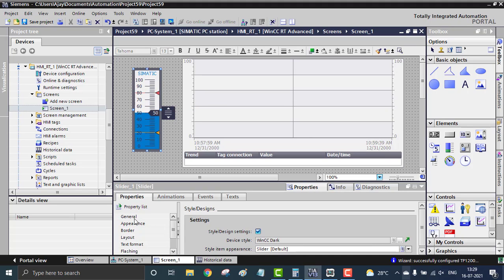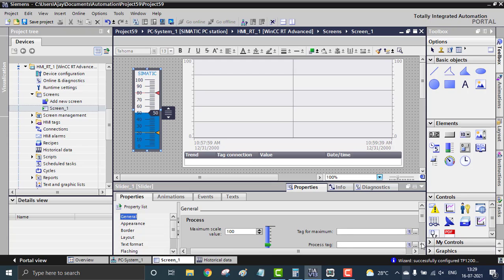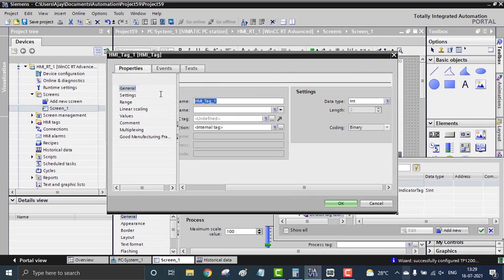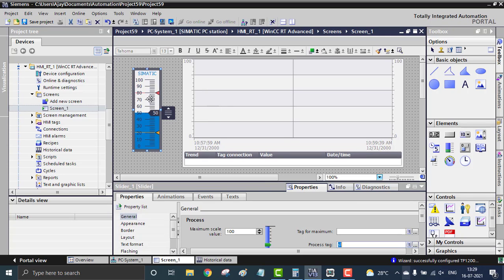Now I want to give the tag name for the trend. Go to General, then Process Tag. I'm going to use a normal HMI tag — go to HMI Tags, then the tag table, and add a new tag. I'm naming it 'sl', which stands for slider. The data type will be Integer. Hit OK. I want to log this tag 'sl' and display it in the trend as a historical trend, so I'm going to create a historical log.